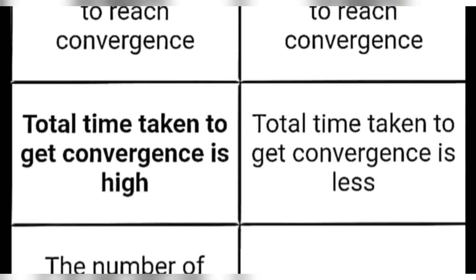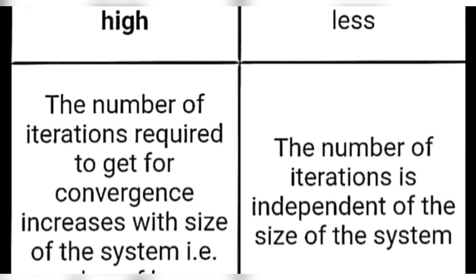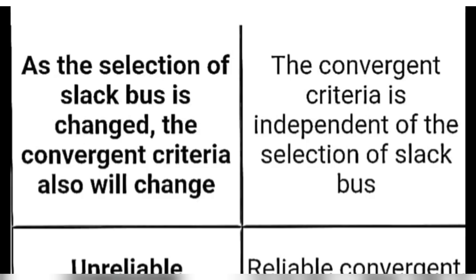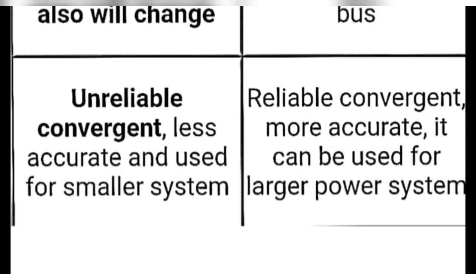Total time taken to get convergence is higher in Gauss-Seidel method, while Newton-Raphson method total time taken to get convergence is less. In Gauss-Seidel method, the number of iterations required for convergence increases with the size of the system, i.e., number of buses. In Newton-Raphson method, the number of iterations is independent of the size of the system. In Gauss-Seidel method, as the selection of slack bus is changed, the convergence criteria also changes. In Newton-Raphson method, the convergence criteria is independent of the selection of slack bus. Gauss-Seidel method is unreliable in convergence, less accurate, and used for smaller systems. Newton-Raphson method has reliable convergence, is more accurate, and can be used for larger power systems.